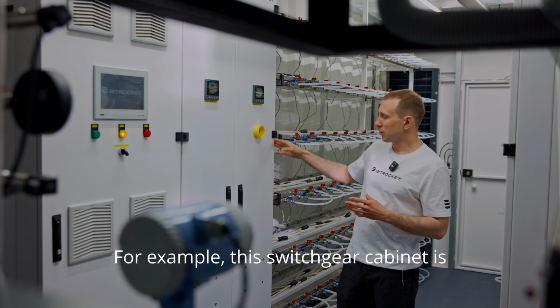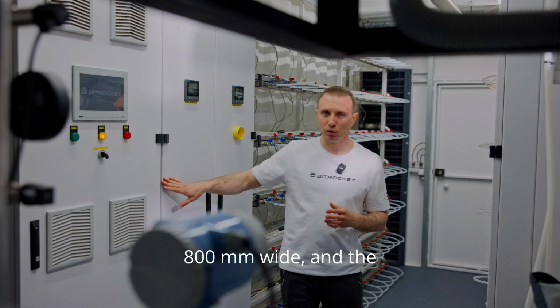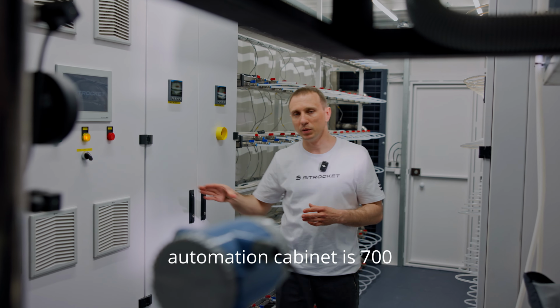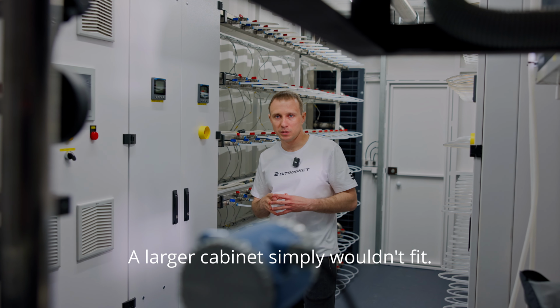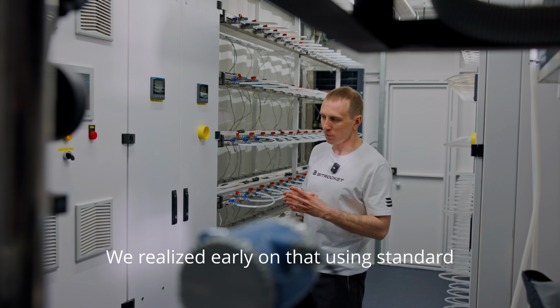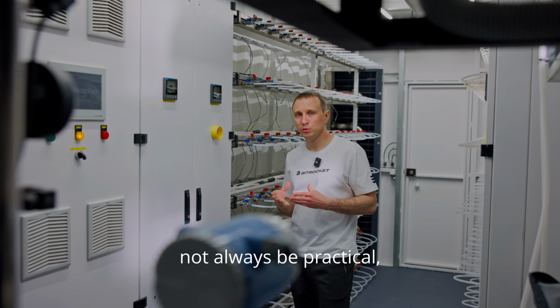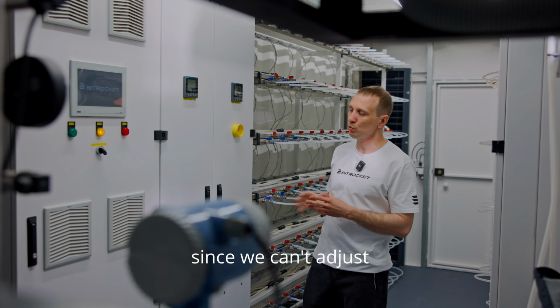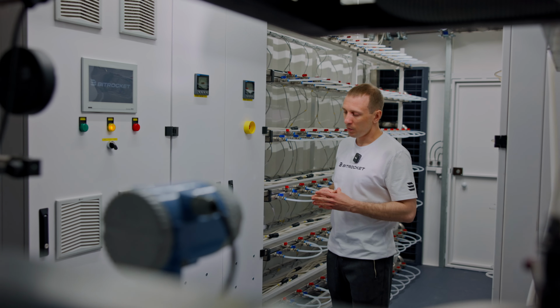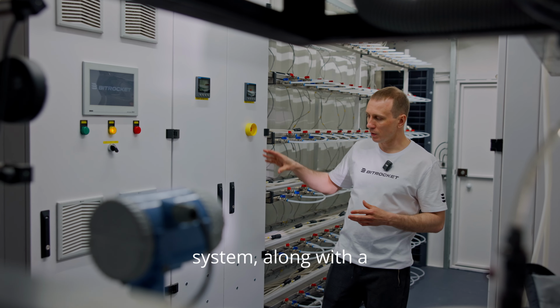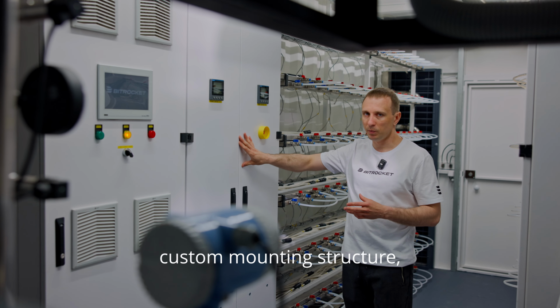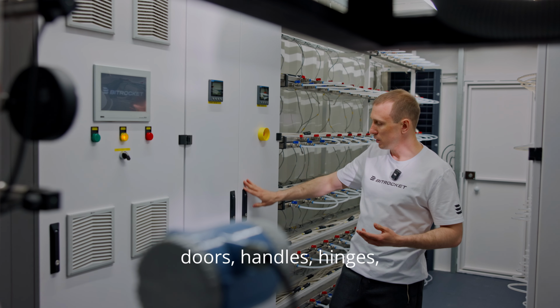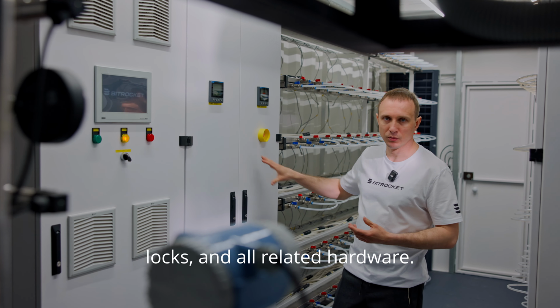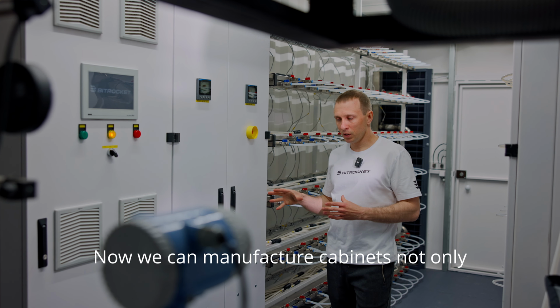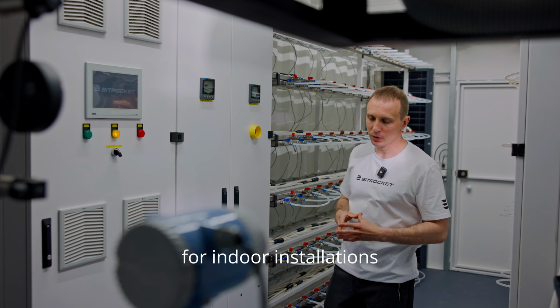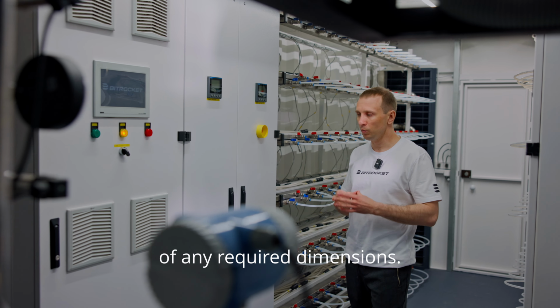For example, this switchgear cabinet is 800 millimeters wide, and the automation cabinet is 700 millimeters wide. A larger cabinet simply wouldn't fit. We realized early on that using standard server racks would not always be practical, since we can't adjust them to suit our needs. That's why we developed our own frame system, along with a custom mounting structure, doors, handles, hinges, locks, and all related hardware. Now we can manufacture cabinets not only for containers, but also for indoor installations of any required dimensions.